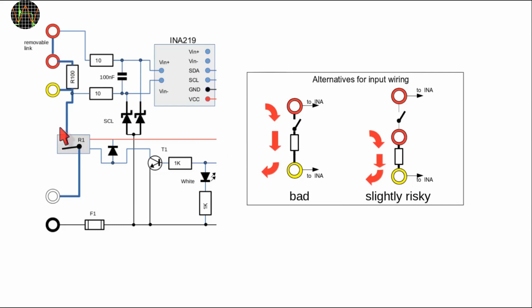Finally, the reason for having both the yellow and white terminals is that the relay contacts are only good for about 10 amps max. So for measuring higher currents with an external shunt, the yellow terminal must be used. The relay contacts, by the way, are outside the current measurement loop, so the on resistance of maximum 30 milliohms does not influence the current readings, but will cause a small drop between the voltage measured by the INA 219 on the yellow terminal and the white terminal. To minimize losses, all current carrying wires need to be as thick as possible.